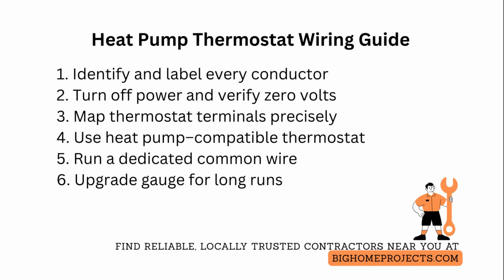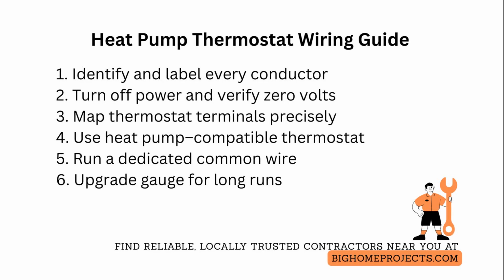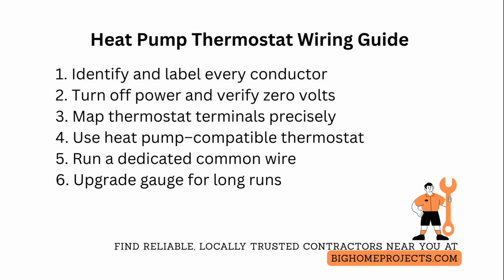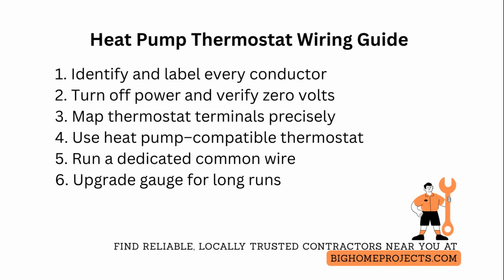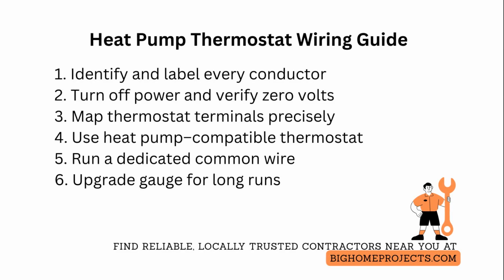For long wire runs over 100 feet, upgrade wire gauge to reduce voltage drop and interference. Use twisted pair for control signals where possible, and keep control wiring away from high voltage runs and motor leads. If the heat pump has a 2-stage compressor or separate strip heat, program the thermostat staging and lockout temperatures and set sensible cycle minimums and maximums to avoid short cycling and unnecessary auxiliary heat.